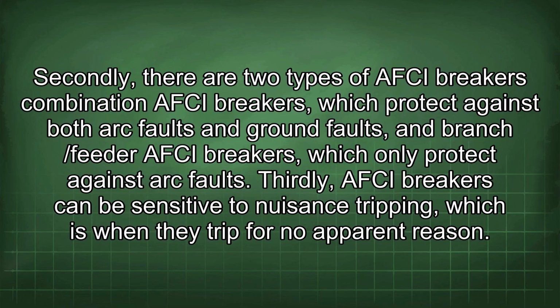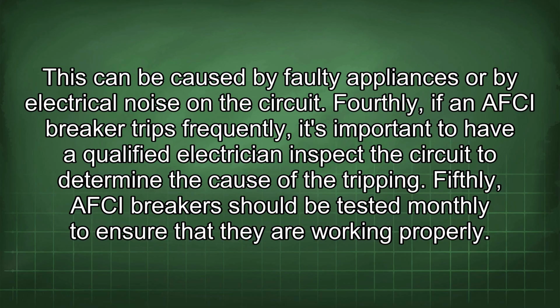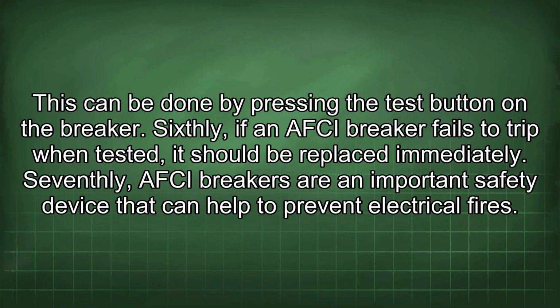Secondly, there are two types of AFCI breakers: combination AFCI breakers, which protect against both arc faults and ground faults, and branch/feeder AFCI breakers, which only protect against arc faults. Thirdly, AFCI breakers can be sensitive to nuisance tripping, which is when they trip for no apparent reason. This can be caused by faulty appliances or by electrical noise in the circuit. Fourthly, if an AFCI breaker trips frequently, it's important to have a qualified electrician inspect the circuit to determine the cause of the tripping. Fifthly, AFCI breakers should be tested monthly to ensure that they are working properly. This can be done by pressing the test button on the breaker.